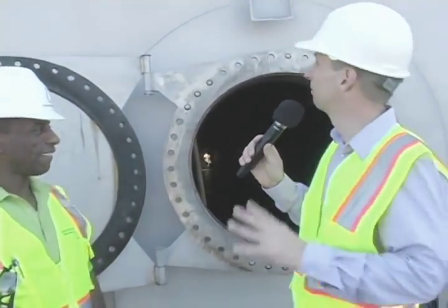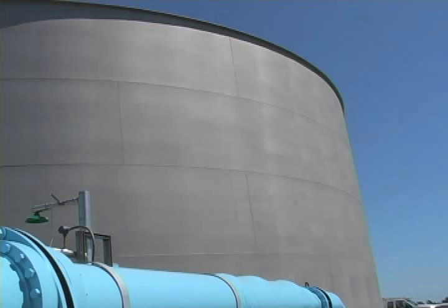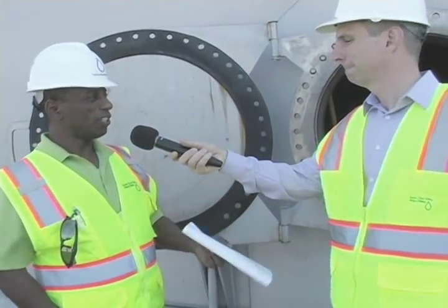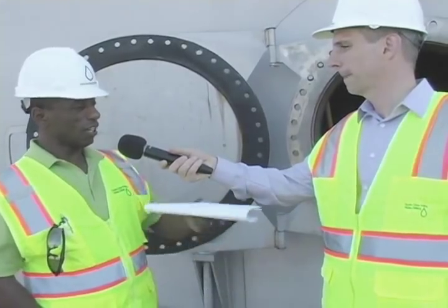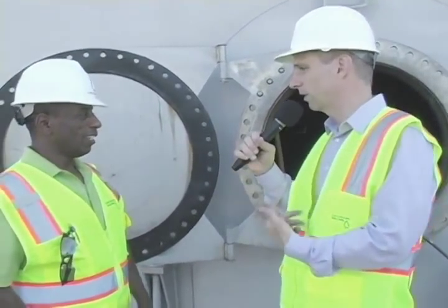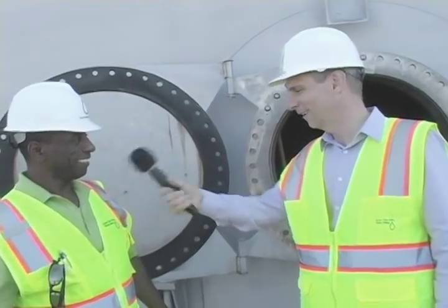We're now at the product water storage tank. This stainless steel welded tank holds about 2.25 million gallons of water — and the facility produces up to 8 million gallons per day. This is our holding storage tank before we send the water to the San Jose Water Pollution Control Plant. We can't go inside because it's a confined space — you have to be properly trained for confined space entry — but it does look impressive with its dome ceiling, and everything is stainless steel so it stays clean.